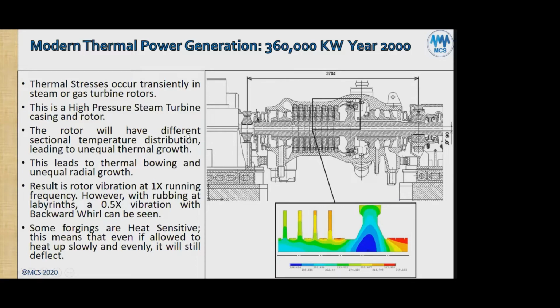So this is a high pressure steam turbine, HP, casing, and rotor. Rotor will have different sectional temperature distribution, leading to unequal thermal growth. So as you can see here on the right hand, you have the red color, the hottest section. We have the blue and the large mass of the main inlet turbine wheel. So the main inlet turbine wheel is having actually a colder temperature in the center because why? To the left are lighter section parts of the rotor, and they will heat up faster. But this is a heavier section, so it takes more time to heat up.